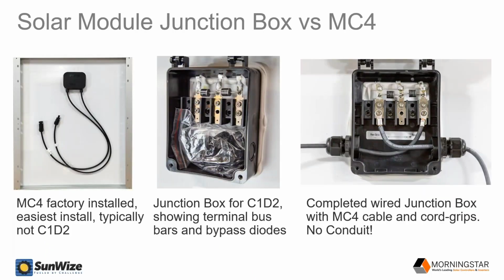Another thing I want to point out about solar modules is this junction box configuration, which is pretty much the standard for all Class 1 Division 2 solar modules. On the left, you'll see an example of a solar module with an MC4 factory installed junction box. While those are very common, I'm not aware of any Class 1 Division 2 solar modules that have that. Typically, a Class 1 Division 2 solar module is going to require a junction box as shown in the middle picture. So that's going to have an exposed area for us to wire and work with the terminal bus bars and the bypass diodes. And so if you're not familiar with how to wire a junction box, that's going to be an important component of working with these Class 1 Division 2 solar modules. And so you can see a picture on the right after everything has been installed, including the knockouts and the cord grips and the wires terminated on the right bus bars. What does that look like?